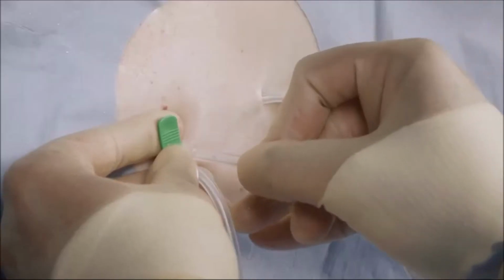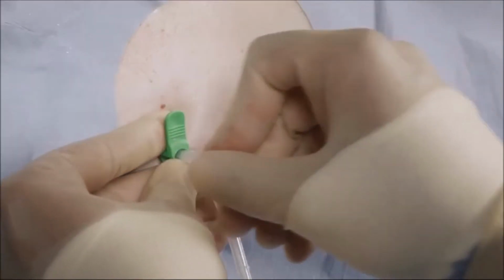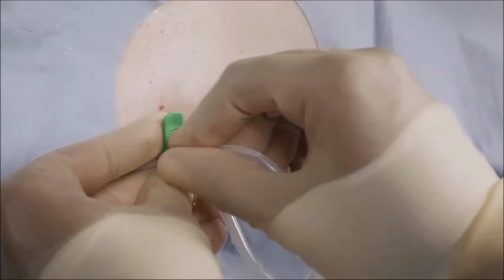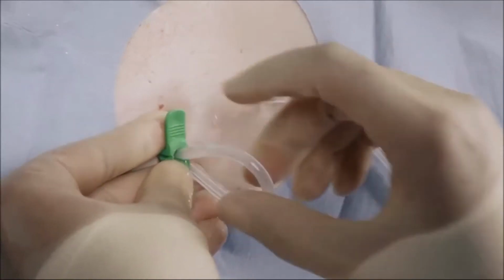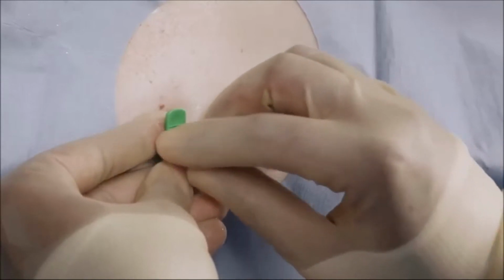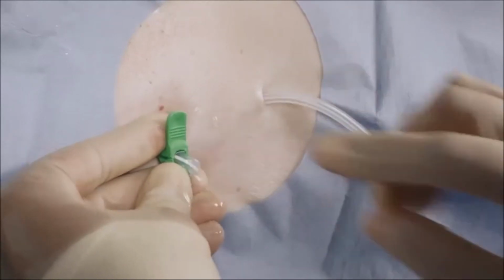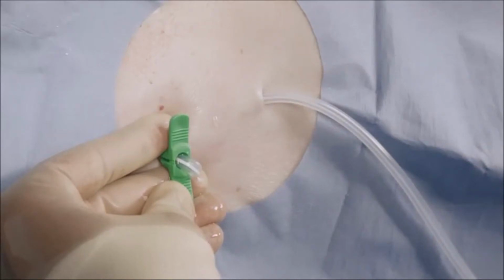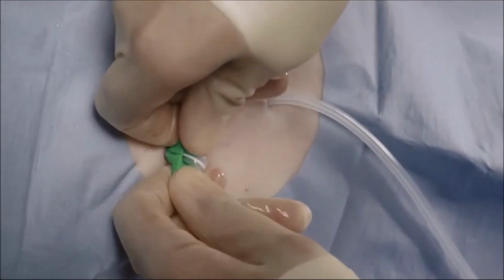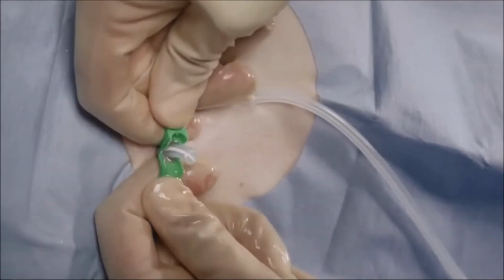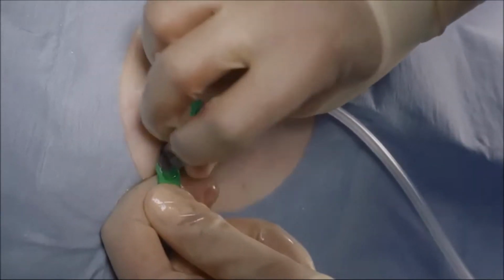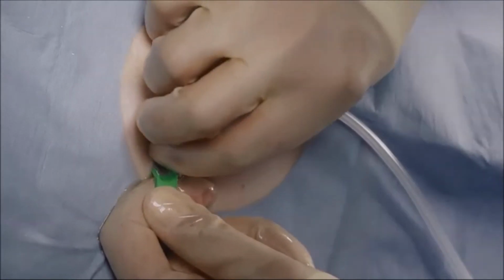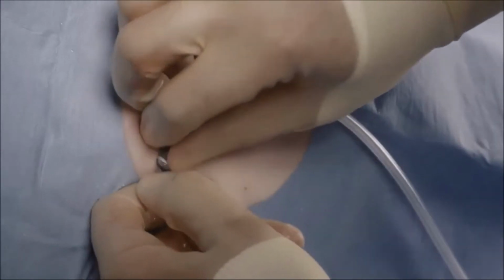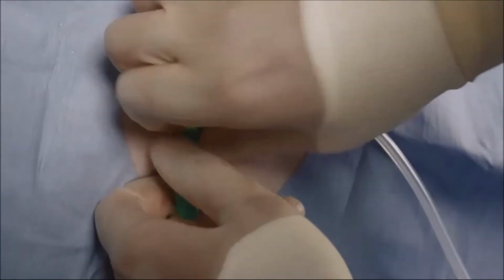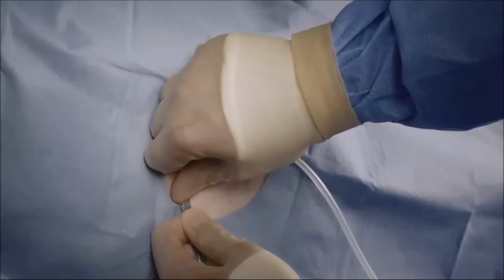Insert the fenestrated end of the catheter into the sheath, advancing it until all the fenestrations are within the pleural cavity. This can be verified under fluoroscopy, as fenestrations are located along the barium sulfate stripe. The fenestrations must be entirely within the pleural space to avoid leakage into the tunnel tract. After the catheter has been positioned, crack the sheath handle in half and peel away the sheath while ensuring the catheter remains in place. Adjust the catheter so that it lies flat in the tunnel without any kinks. Do not use forceps on the introducer to break the handle and/or peel the sheath.